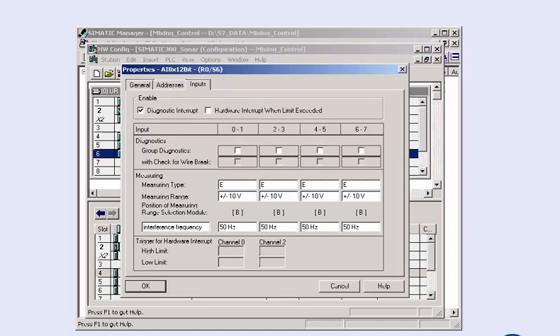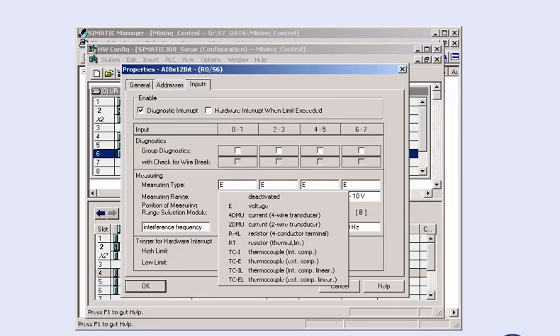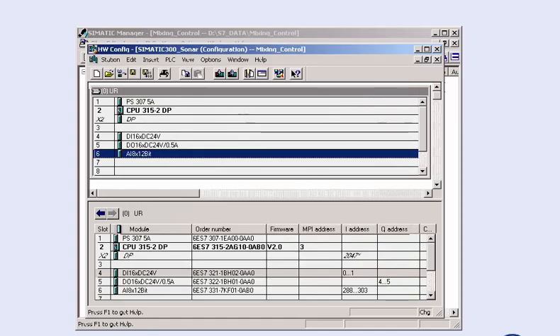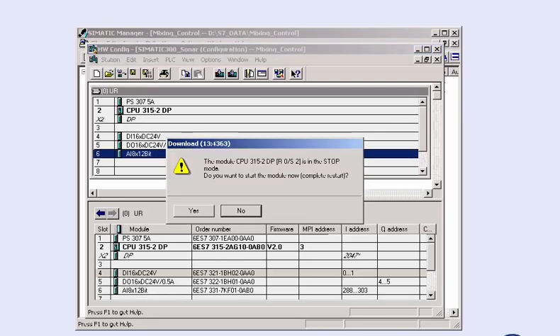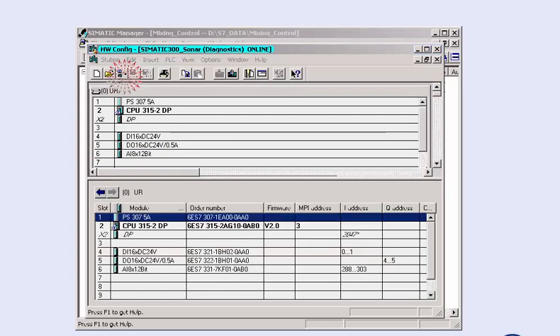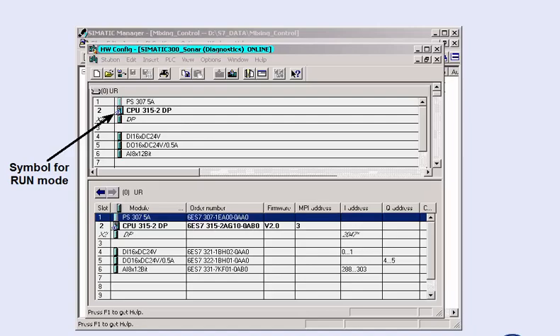For channels 0 and 1, the measured range plus minus 10 volts is the wrong default setting. In the offline project, we correct the measured range, save and compile the change configuration. Subsequently, we re-transfer the configuration and start the CPU. The CPU remains in run mode and there is no longer a diagnostic interrupt.